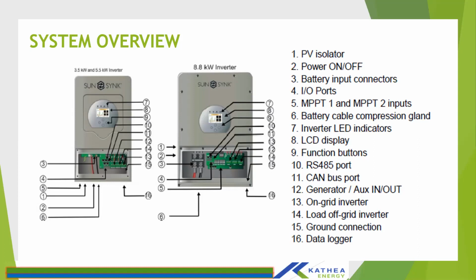The inverter supports CAN bus and RS485 for battery integration. We mainly distribute the SunSynk inverter with a Freedom Won battery, which supports CAN bus. So all you need is to match the CAN bus pins to the battery type that you'll be using, that is, if it's lithium. If it's gel batteries, the inverter also supports a wide range of batteries, from lead acid and gel batteries, and mostly now in the market, people are using lithium.